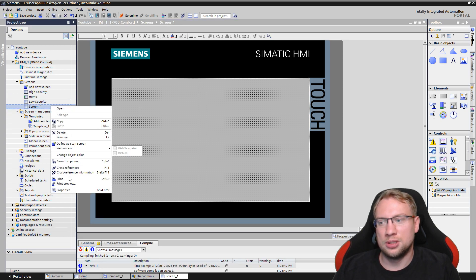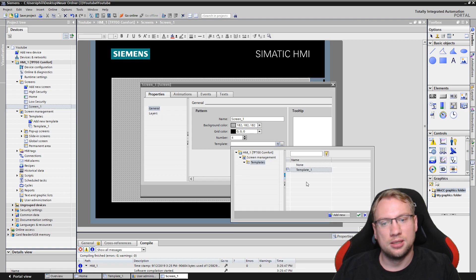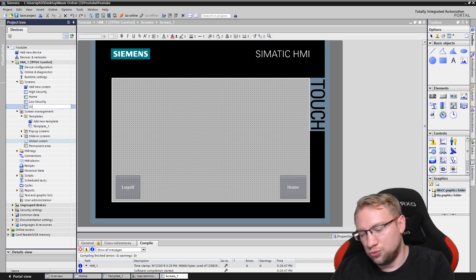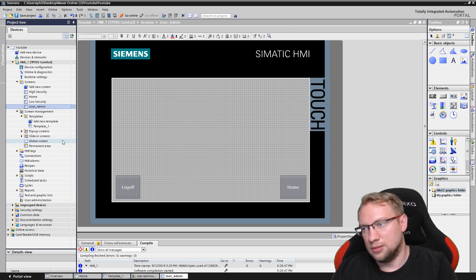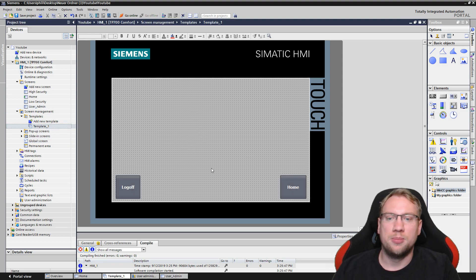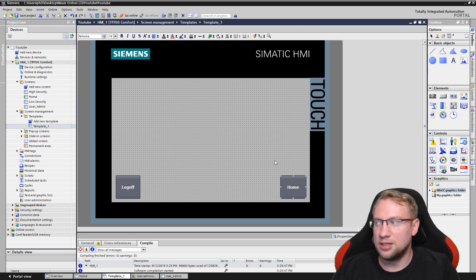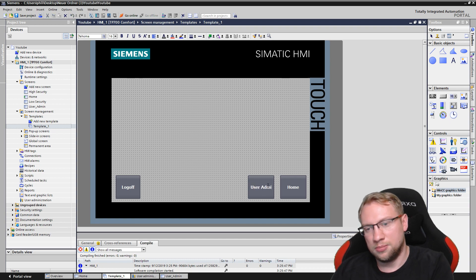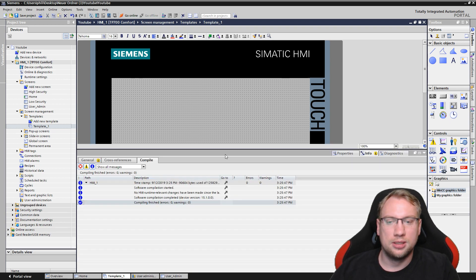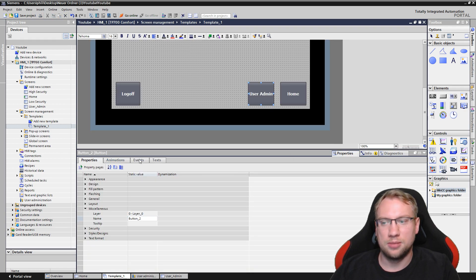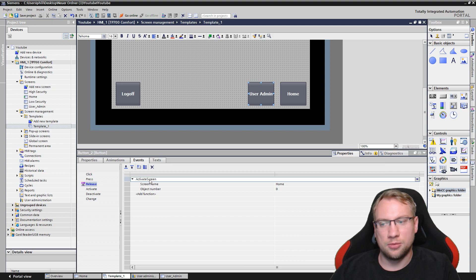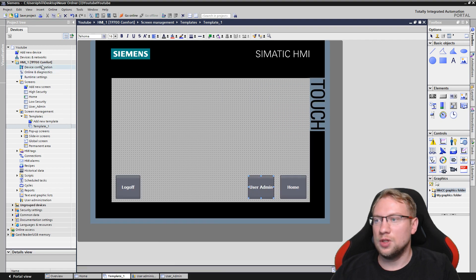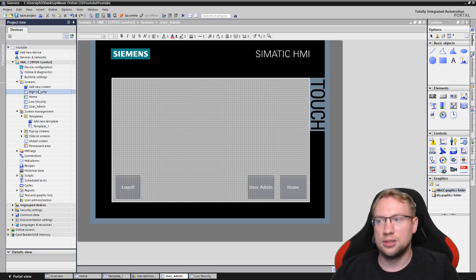What we will do now is add a new screen. I also want to use a template — template one — so it looks like the others and has a home and a log off button. I'll give it the name 'user admin'. I also want to be able to get to the user admin from every screen, so I'll copy and paste a button, label it 'user admin', and set the release event to activate the user admin screen.